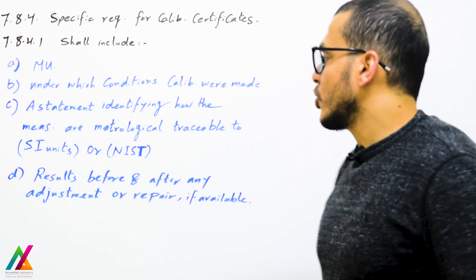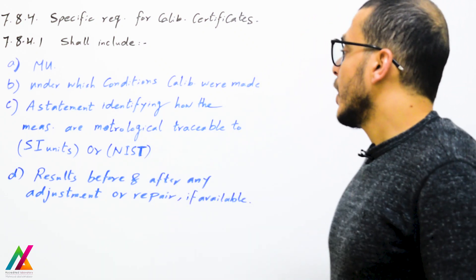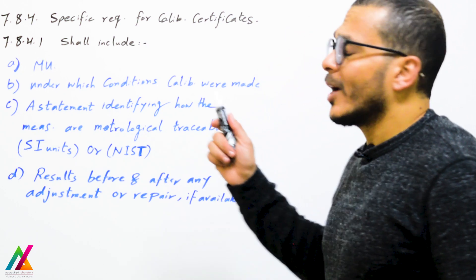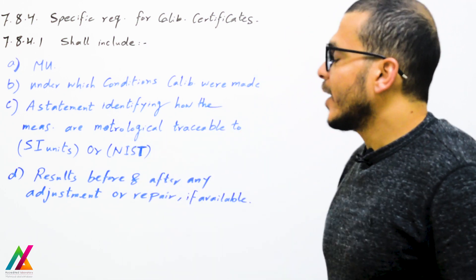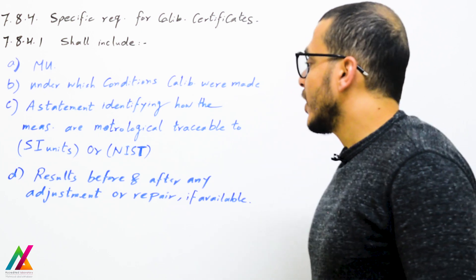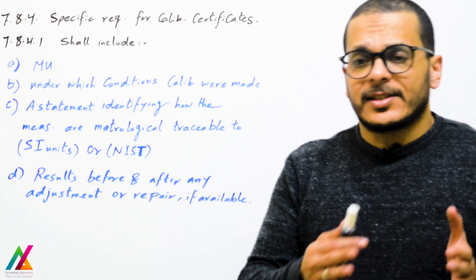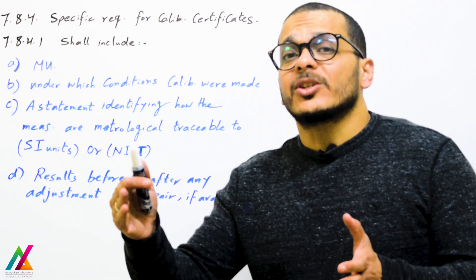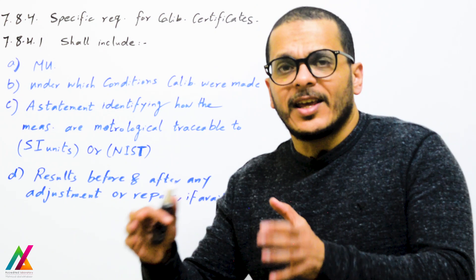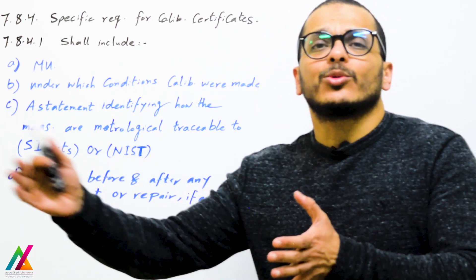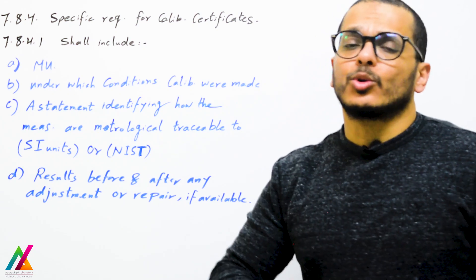Metrological traceability for results shall also be included in the calibration certificate — a statement identifying how the measurements are metrologically traceable to SI units, the International System of Units, or to NIST, the National Institute of Standards and Technology. You can write that values were traceable to national standards, and that national standard is in turn traceable to SI units.